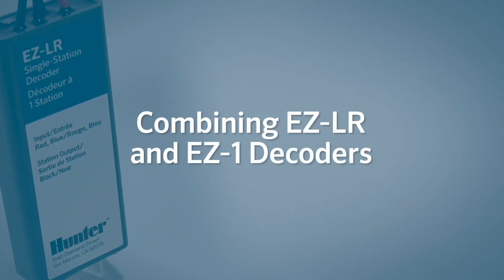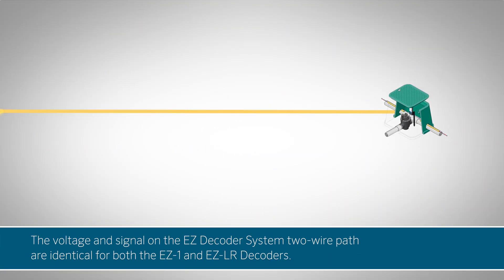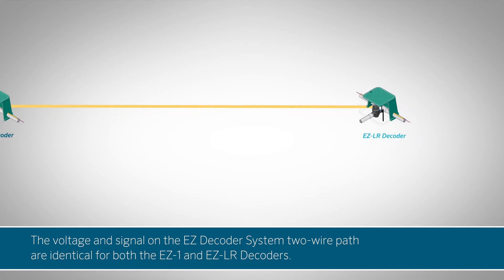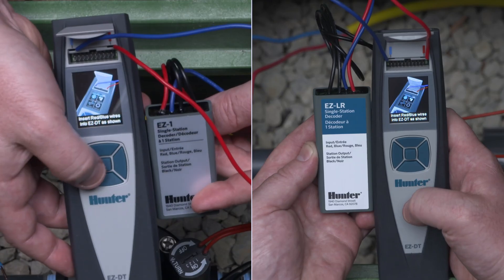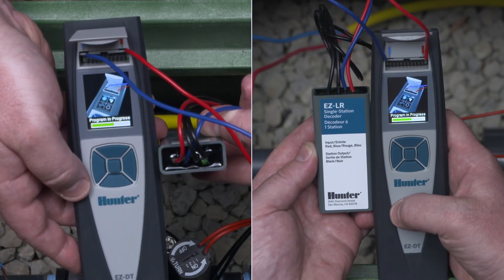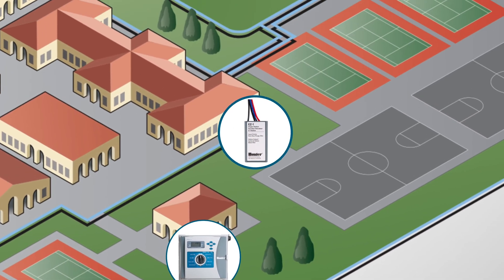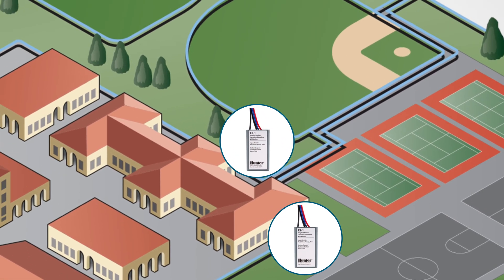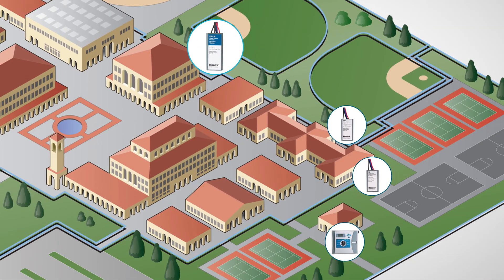Combining EZ-LR and EZ-1 decoders. The voltage and signal on the EZ Decoder System two-wire path are identical for both the EZ-1 and EZ-LR decoders. This compatibility allows you to seamlessly combine them on the same path with a single installation. Use cost-effective EZ-1 decoders for nearby valves and long-range EZ-LR decoders for distant valves on the same wire run to optimize system design and cost.